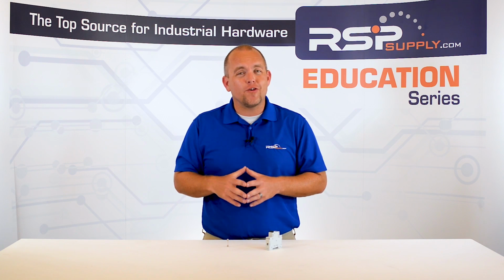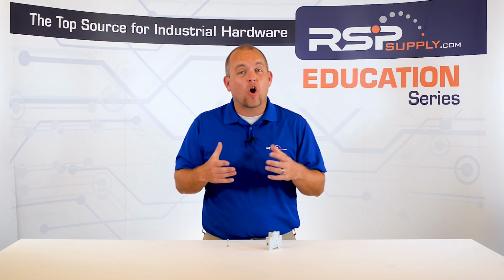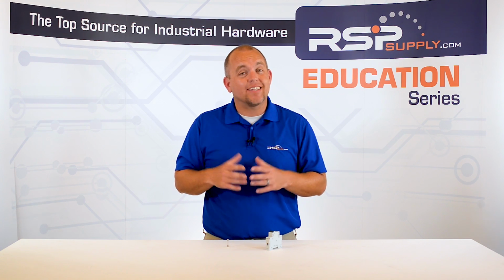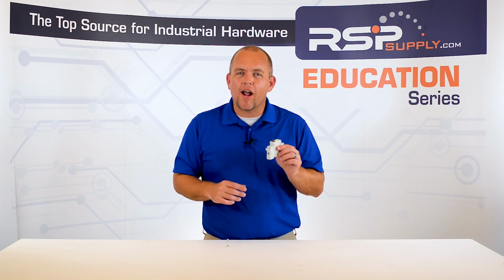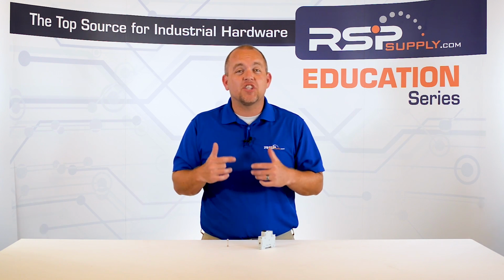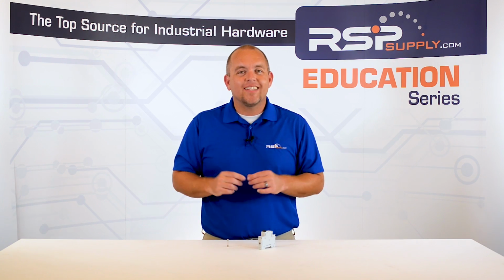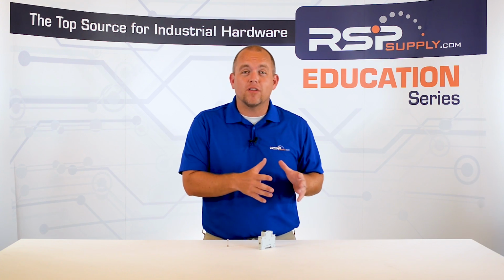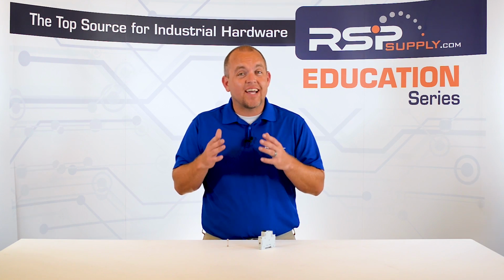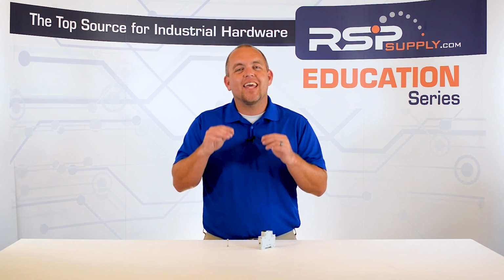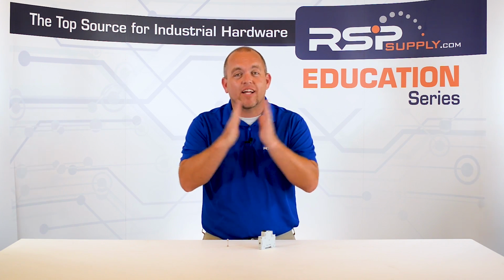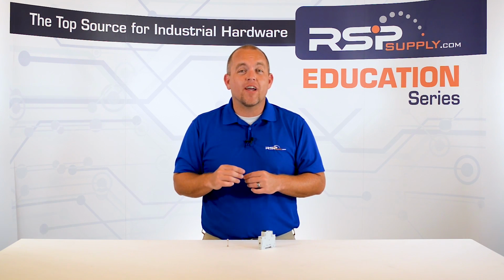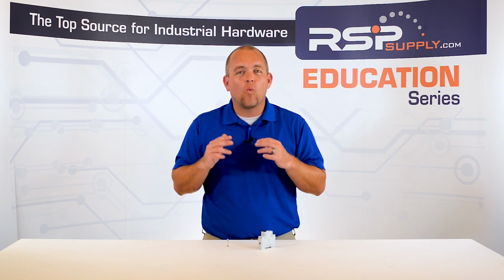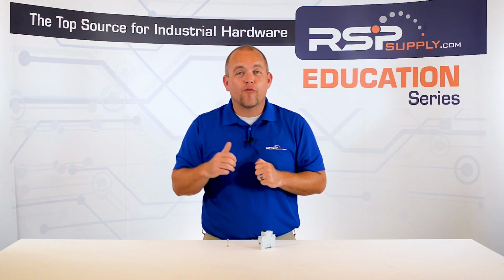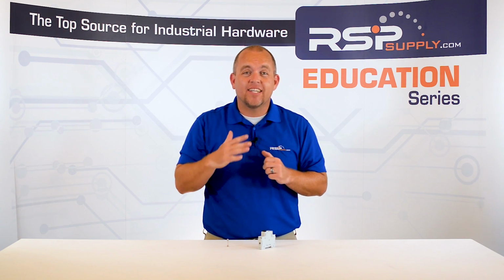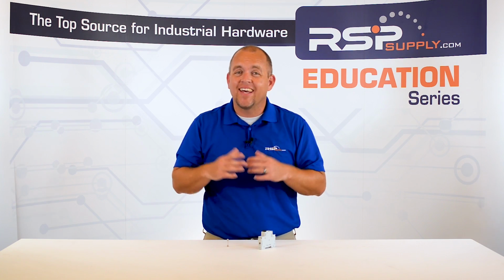Another disadvantage of using a fuse is that the electrical connection points are often exposed and can create a safety hazard. By using a circuit breaker, you eliminate the need to replace the unit each time a surge occurs. This is because the circuit breaker functions very differently. Instead of burning a piece of sacrificial wire like a fuse, it interrupts current by disconnecting electrical contacts. When the circuit breaker is reset, those contacts will once again become connected, allowing current to pass through the circuit until another surge or overcurrent event is seen.